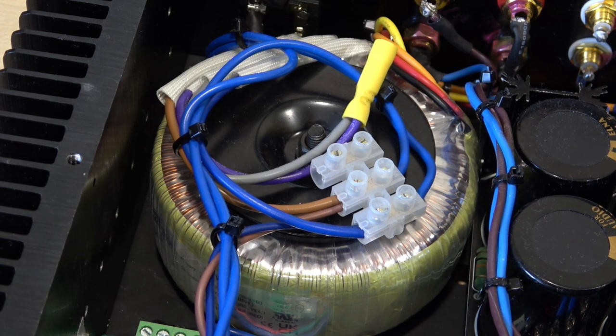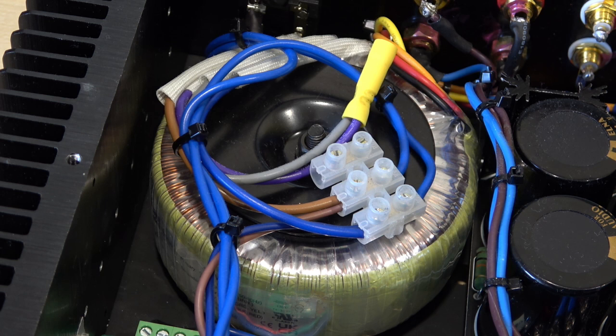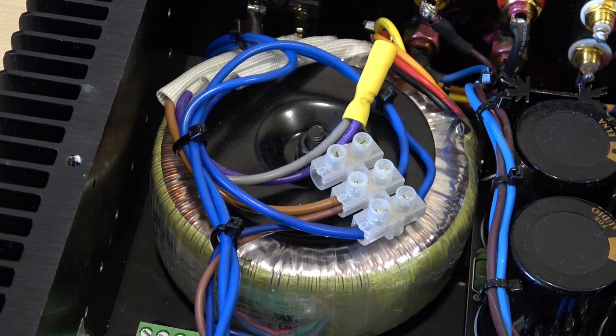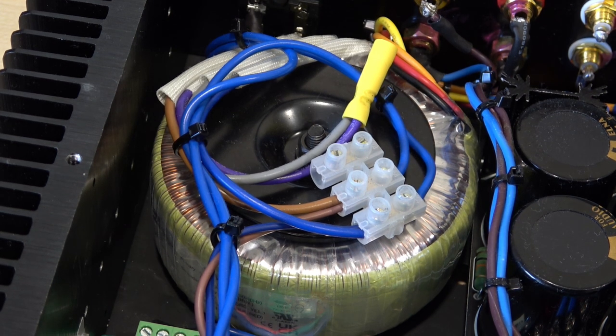This particular transformer came from a company called Farnell, now called Element 14 for some strange unearthly reason, but we all call it Farnell and probably will for the next 100 years. Whilst it was made in China, it's built to European standards, so if it says 160 VA, that's really what it will do all day and all night. Whereas if you get one from China directly, the chances are it won't — it'll be smaller, lighter, and might even be wound with aluminium wire instead of copper. You'll probably, in all honesty, be able to buy it cheaper from your local company.